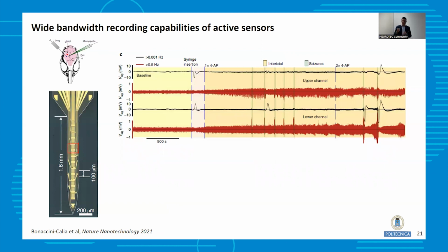Okay, so I'm going to show you some of the recording capabilities, for those of you who are doing electrophysiology. This is an example of what we call the wide bandwidth recording capabilities of the active sensor. This is a recording from an intracortical device that goes across the cortex. This is non-multiplexed; I'll show multiplexed later on. There are 16 devices here recording from different layers in the cortex. This is an example of the recordings: two channels, the two lines on the top and the two lines at the bottom. Each corresponds to a different channel. The black corresponds to what we call the full bandwidth, including the infraslow activity, and the red corresponds to the standard AC recordings that you can get with passive electrodes.